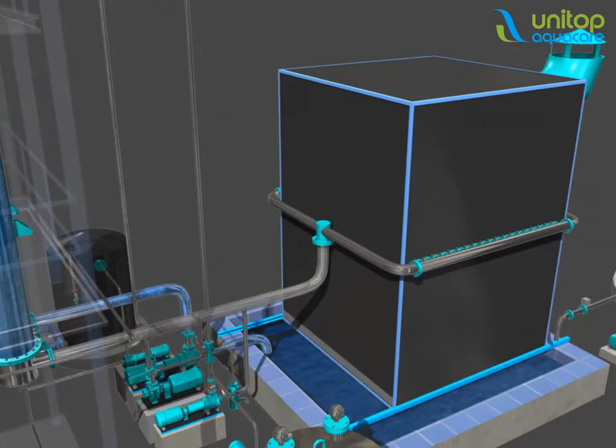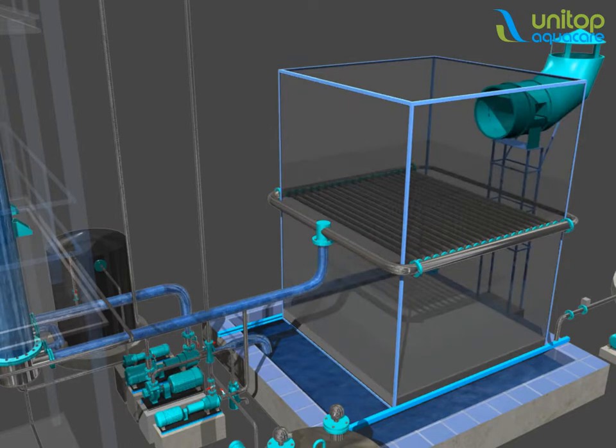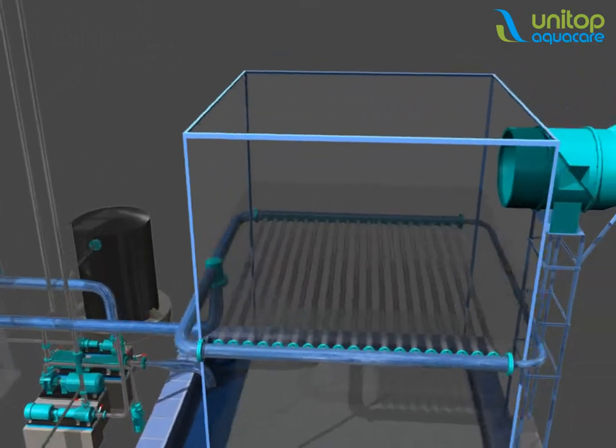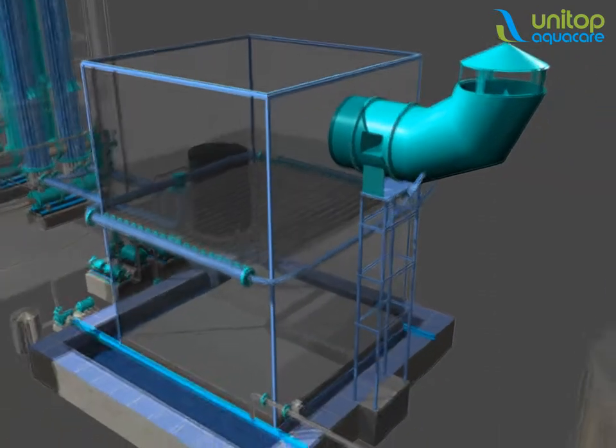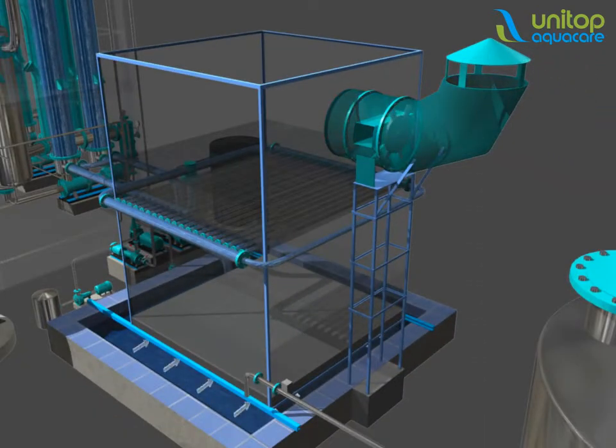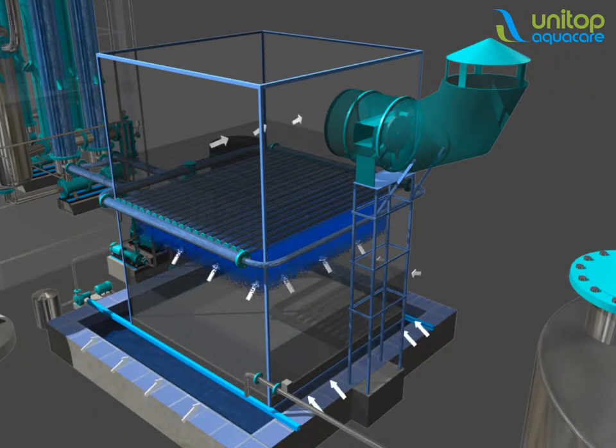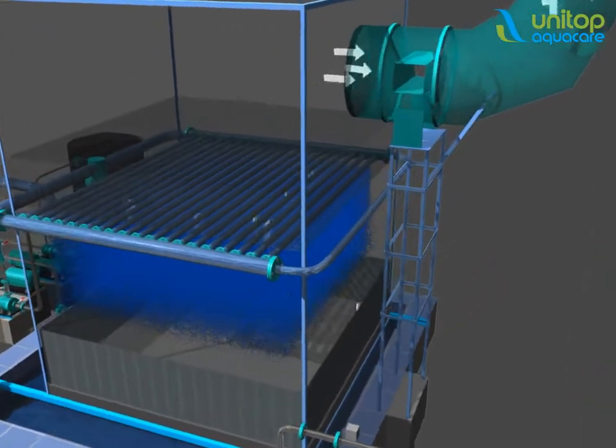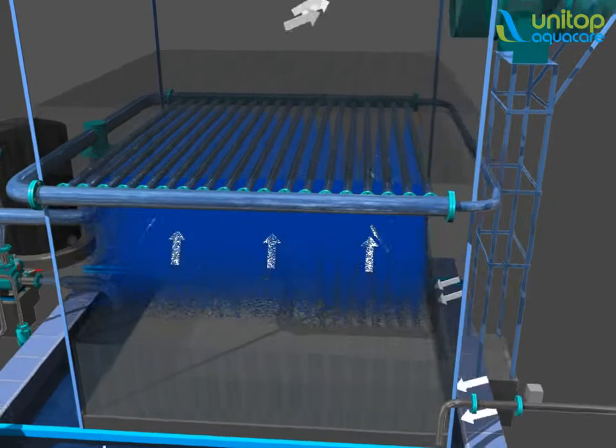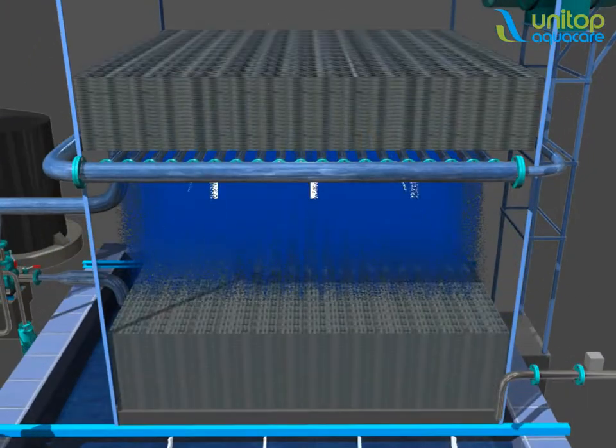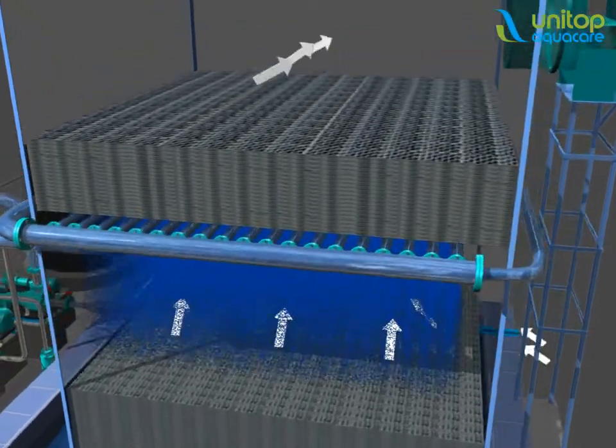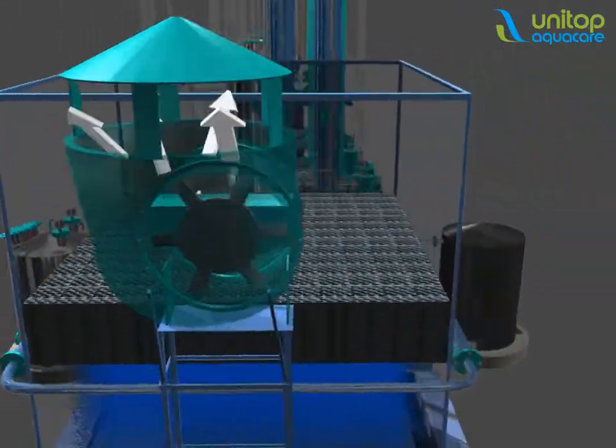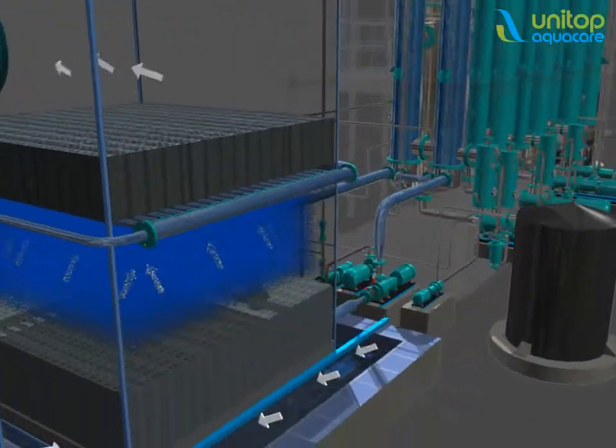During the process, the sensible heat in the liquid is used to evaporate the water in the feed, which comes to you free of cost, saving a lot of steam. The hot liquid is sprayed in the adiabatic evaporator through evaporative coils and gets cooled by fresh draft of cold air. This method not only saves steam but also removes the requirement of a cooling tower from the system.